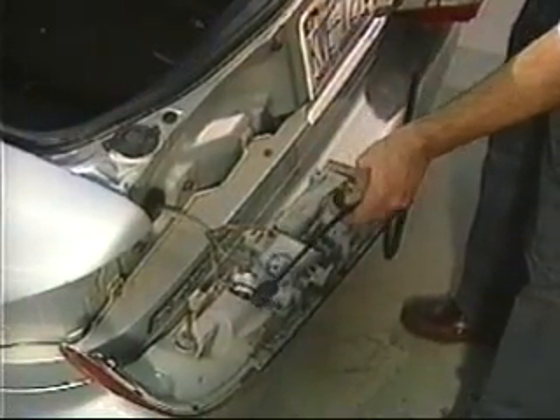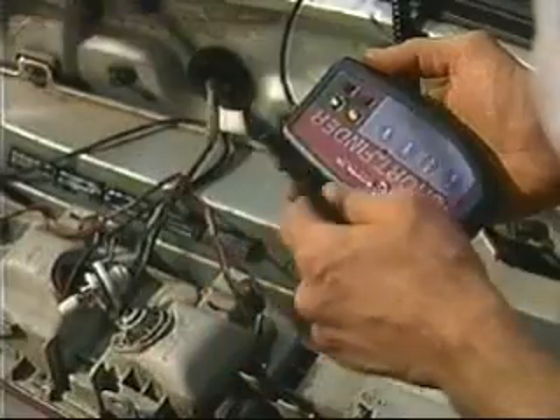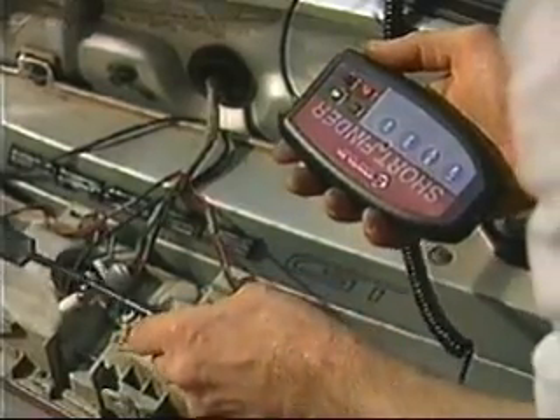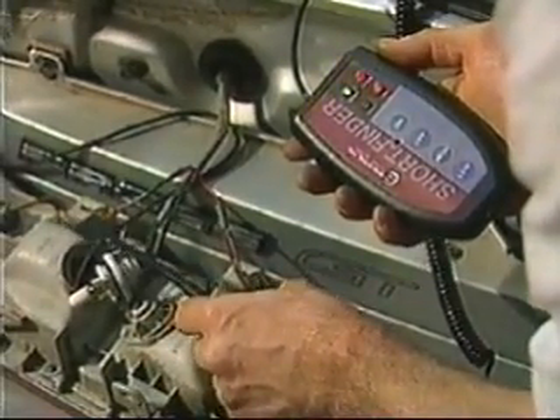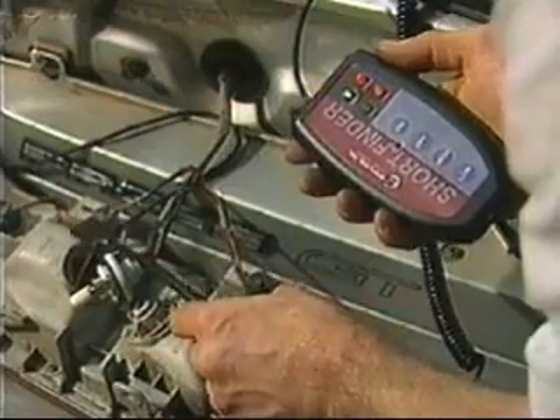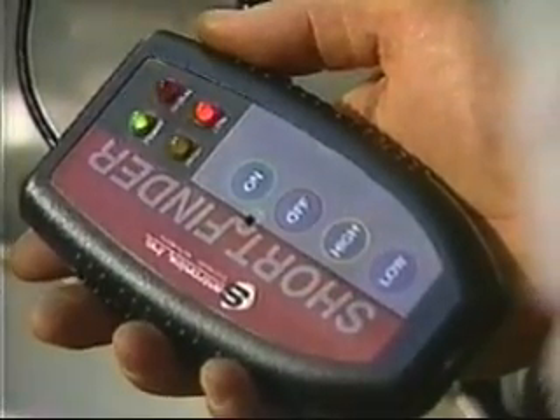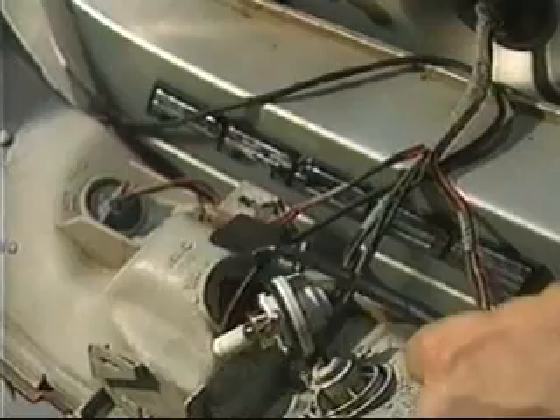The signal will stop in the general area of the short. Set the sensitivity switch to low for the narrow search and carefully scan the area of the short again with the probe. You should be able to pinpoint within inches the area you need to search for the short.